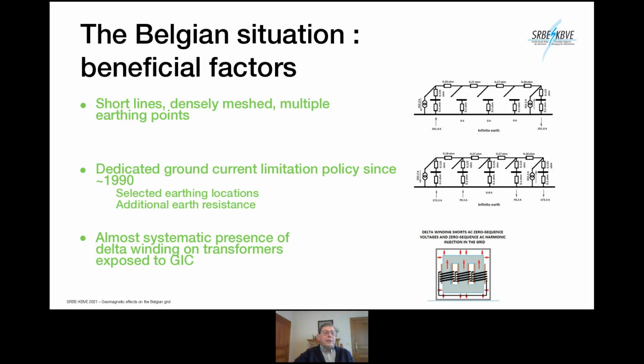A second interesting factor in Belgium is that the utility operator, since almost 30 years, has selected a grounding policy to minimize the earth fault currents, but still in agreement with the general principle of effectively earthed network, which was chosen for the Belgian design.